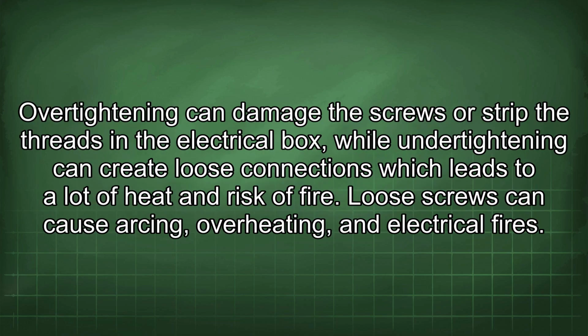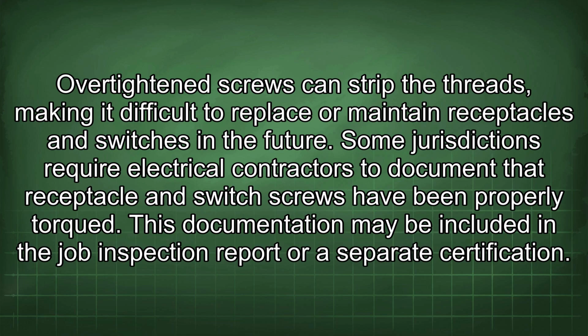Over-tightening can damage the screws or strip the threads in the electrical box, while under-tightening can create loose connections, which leads to a lot of heat and risk of fire. Loose screws can cause arcing, overheating, and electrical fires. Over-tightened screws can strip the threads, making it difficult to replace or maintain receptacles and switches in the future.